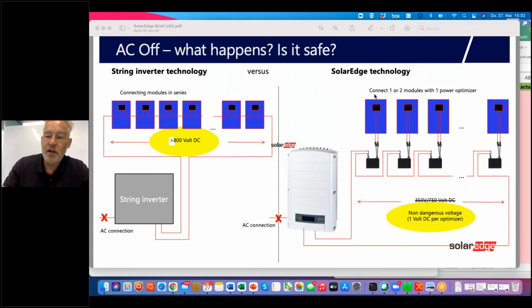With SolarEdge, the firefighter switches off the AC connection, the power supply to your inverter. Each panel still creates 40 volts because we cannot switch off the sun. But now the 40 volts go into the power optimizer, which recognizes that the SolarEdge inverter was switched off. So it says, I will not pass voltage to the inverter because the inverter is gone, and it gives at the output automatically 1 volt, meaning my total voltage on the DC cables is now only maximum 50 volts.